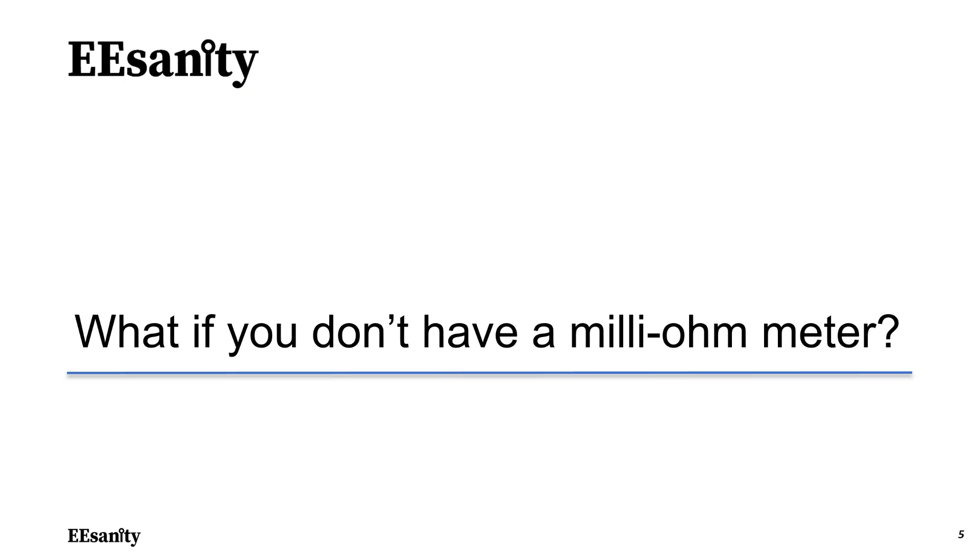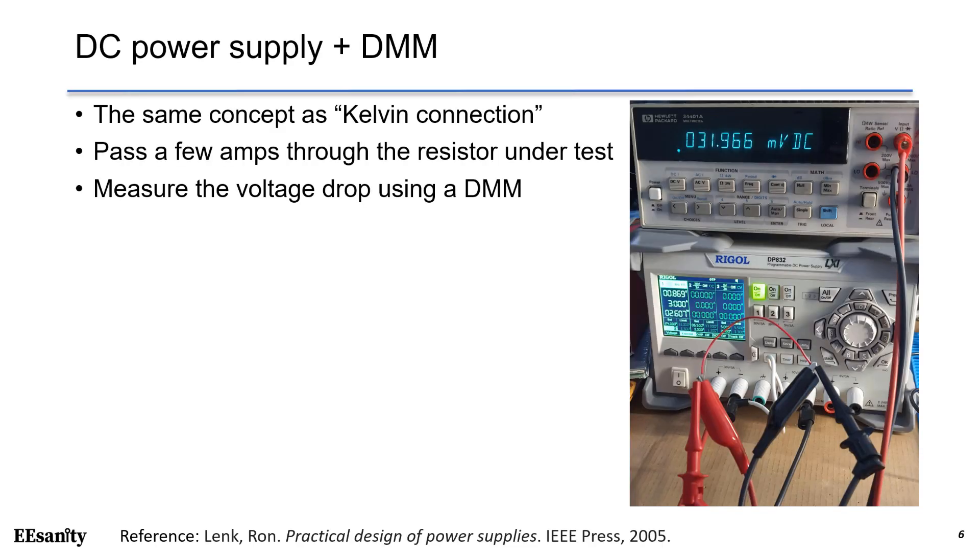What if you don't have a milli-ohm meter? This is another solution using a bench power supply and a digital multimeter. This is the same concept as Kelvin connection in milli-ohm meters. We need to pass a few amps through the resistor under test, and we measure the voltage drop across the resistor using a multimeter.